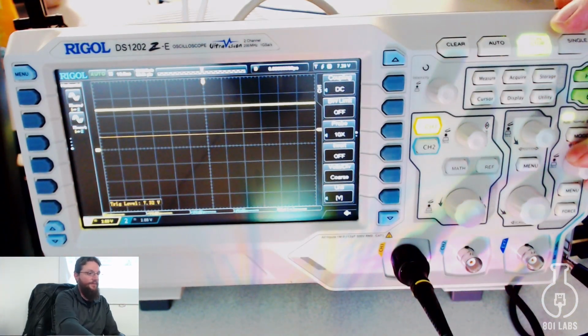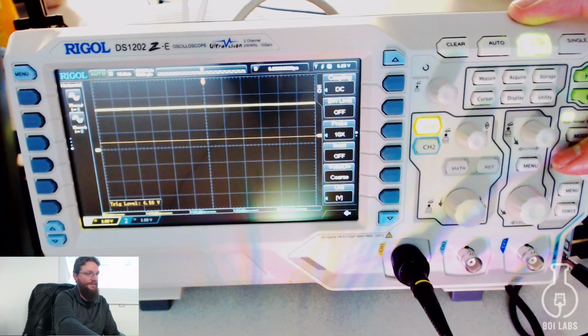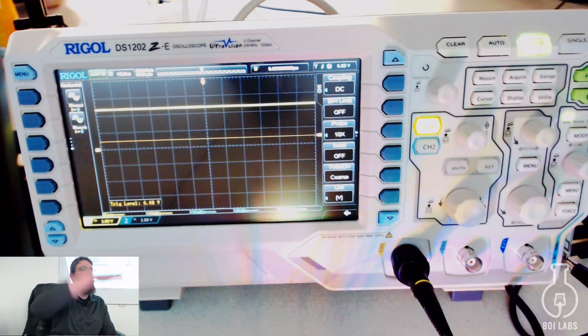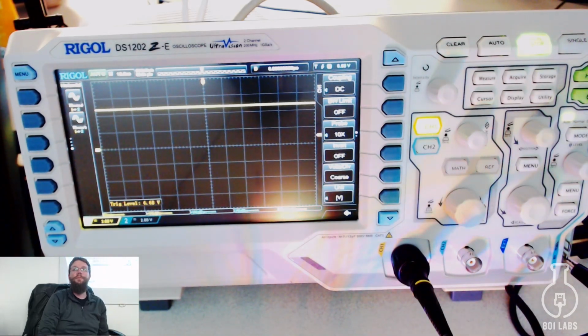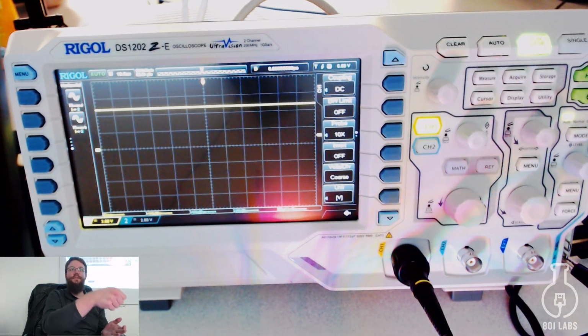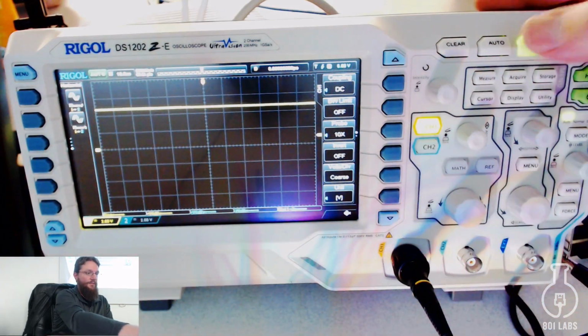I also preset the trigger to be slightly higher than ground, so if it went up, it would refresh the scope. If it doesn't go over your trigger value, the screen will just stay wherever it was, and you can connect it to 100 things, but if your trigger's set at 23 volts and all your signals are at 5, it's never going to turn on. So you can prime the pump like that.